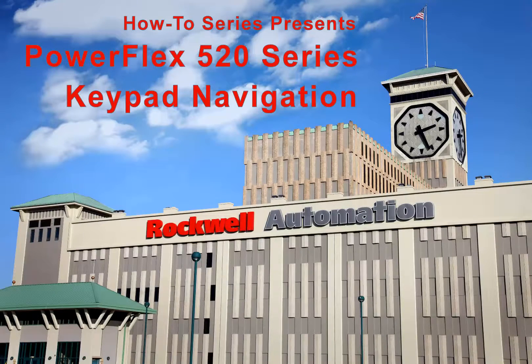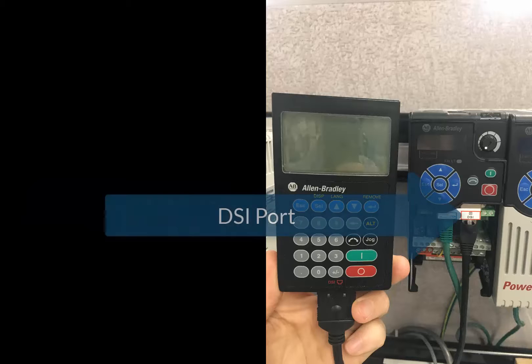The following video will illustrate how to successfully navigate the keypad on the PowerFlex 523 and PowerFlex 525. Both of these drives come with integral keypads that function as a method of parameter programming, drive diagnostics, and basic motor control such as start, stop, and speed reference. The keypad is not to be confused with the HIM, or Human Interface Module, which is an accessory that plugs into the DSI port on the drive.